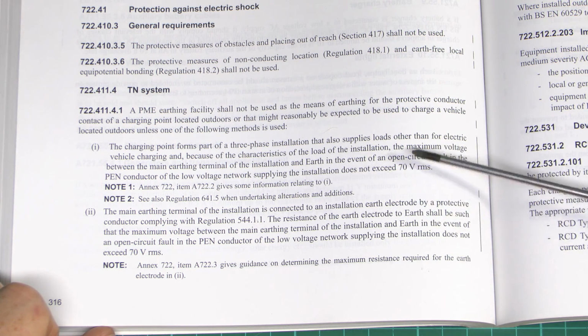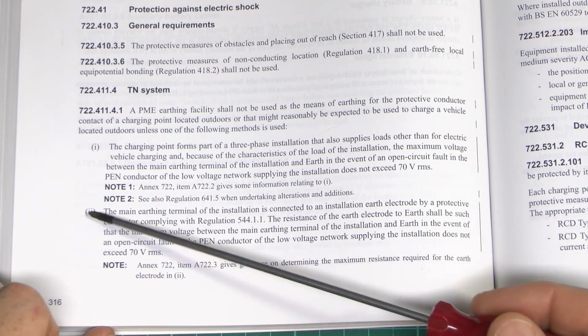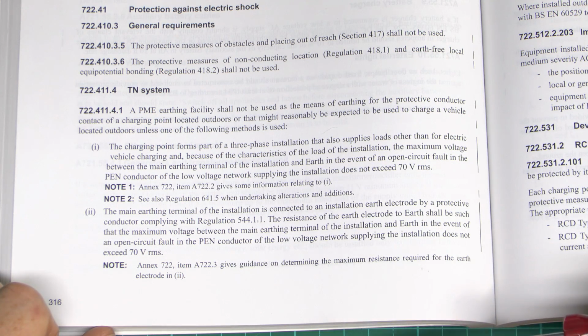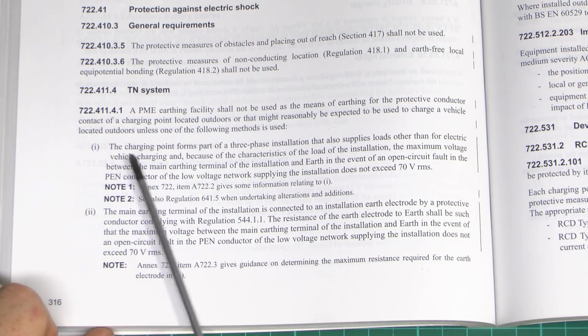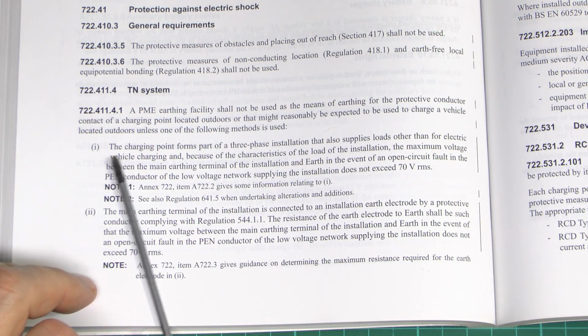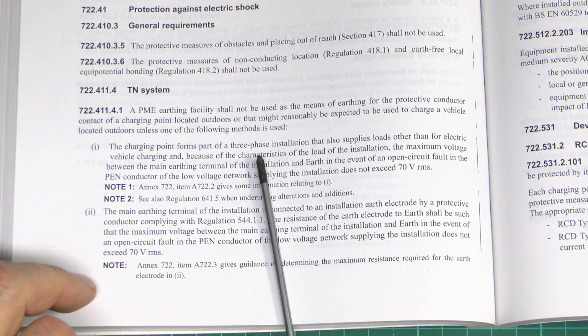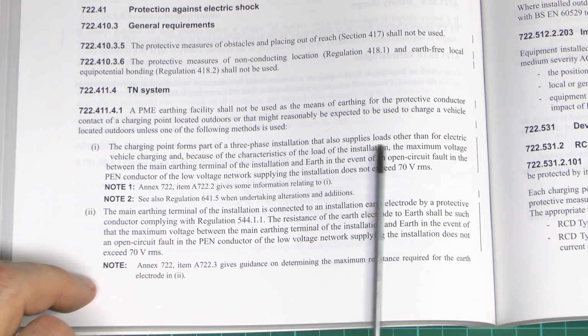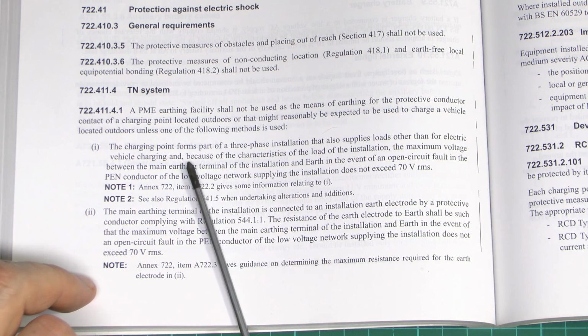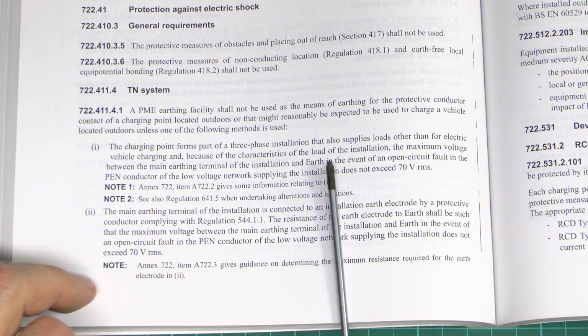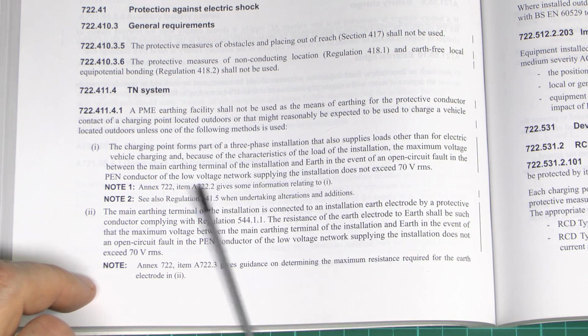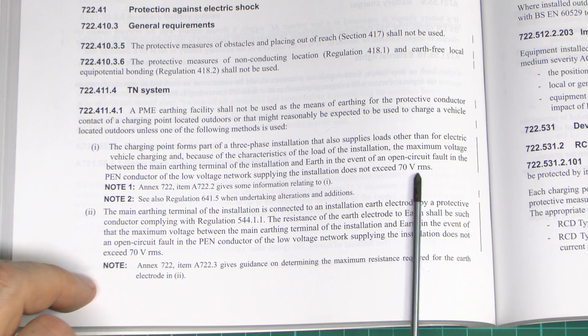But in theory, if you did manage to comply with one of 1, 2 or 3, then you could, in theory, use the PME earthing facility. But just have a look at the first one here. So the first one is that the charging point forms part of a three-phase installation that also supplies loads other than for electric vehicle charging, and because of the characteristics of the load of the installation, the maximum voltage between the main earthing terminal of the installation and earth in the event of an open circuit fault in the PEN conductor does not exceed 70 volts.